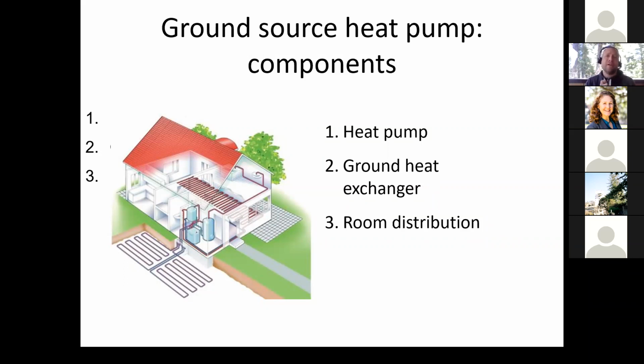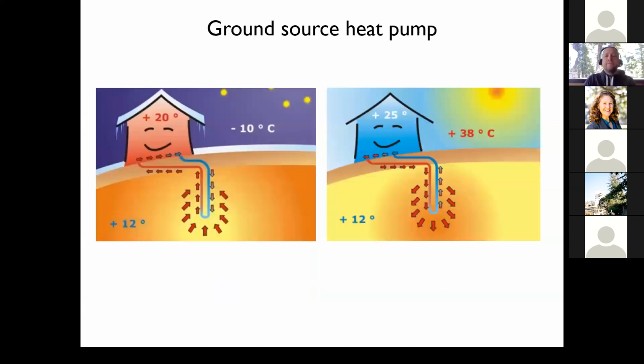Ground source heat pumps work best when, over the course of an entire year, your heating loads and cooling loads are about the same, because we're really just using the ground as a battery. If you have too much heating load and you're always extracting heat from the ground, eventually you'll cool the ground down and lose capacity in your system. That's why we don't see a lot of these systems in places like Alaska, where most of the load is heating load - you'd need an enormous field to avoid degrading the ground temperature. So we're just storing energy in one season and dumping it back in the other, and you really want those to be balanced, or the ground temperature will change.